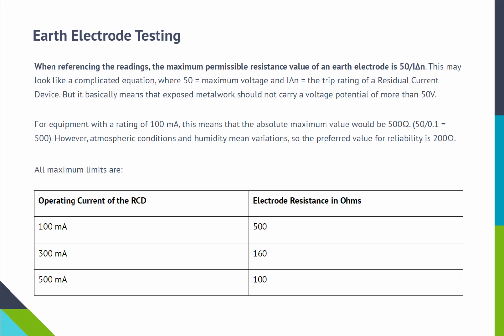For equipment with a rating of 100 mA, this means that the absolute maximum value would be 500 ohm. 50 by 0.1 equals 500. However, atmospheric conditions and humidity mean variations, so the preferred value for reliability is 200 ohm. All maximum limits are.